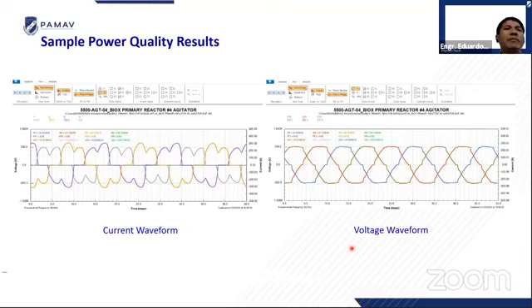So here we have a sample power quality result. This example is an agitator motor with a VFD. If we know that it's a VFD, we know that there is distortion. If we look here, we have the current and the voltage. Look at my graph here. See, this is my sine wave. This is per cycle, and to complete the whole cycle, this is the half cycle. So it is not a pure sine wave. Why? Because of the harmonics present from the VFD.